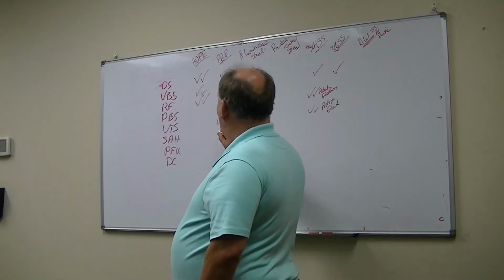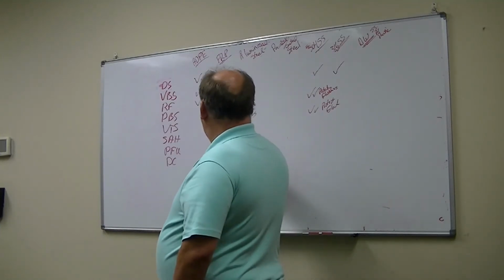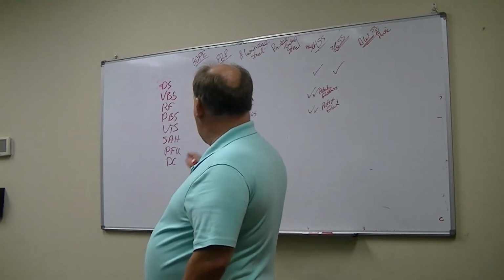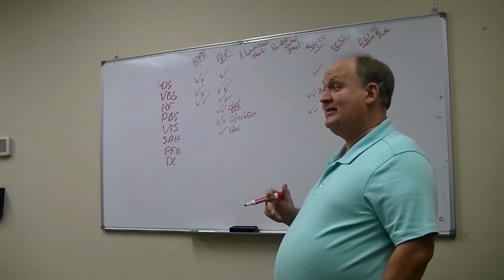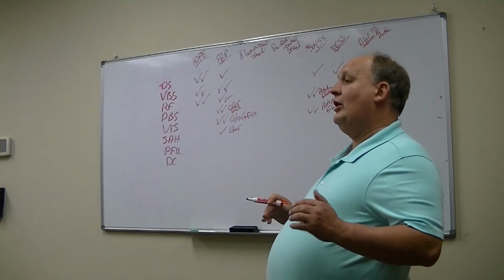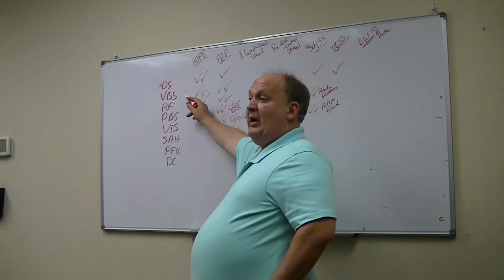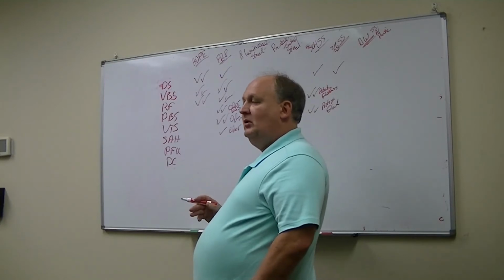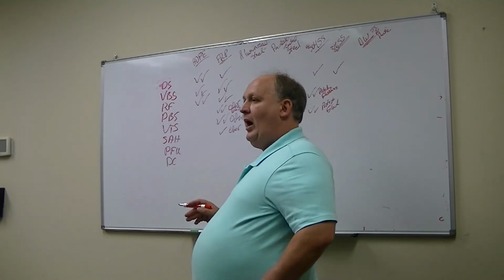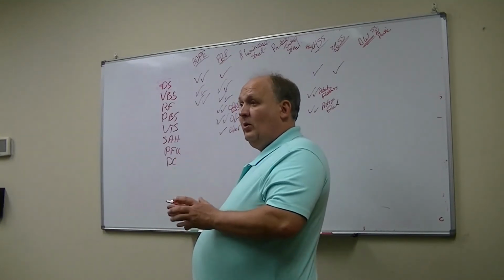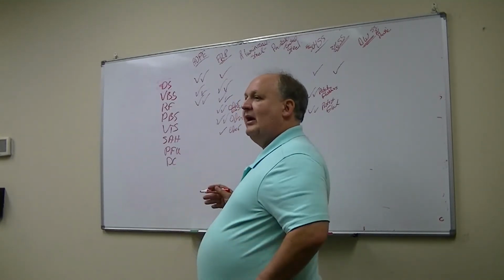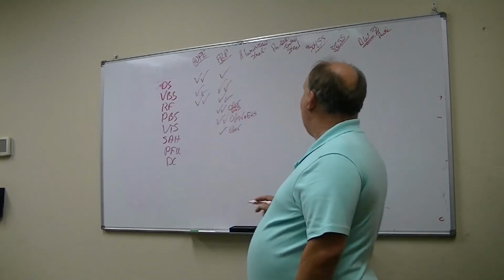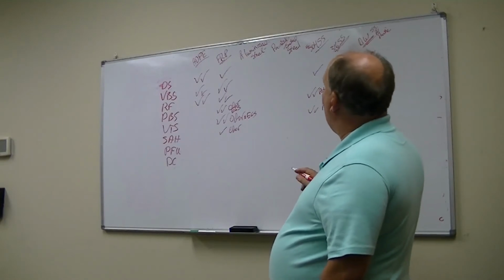Interesting enough, we've done some SAH units for odor. Okay, I'm only going to give it one check there because typically, as I was saying before, a higher odor control requires a deep bed unit, and typically a cassette unit's not good for odor control. But we've run into some special cases where a customer had a very tight space and a very low odor level, and we were able to make a SAH unit work for them. All right, so that's an option that we have.